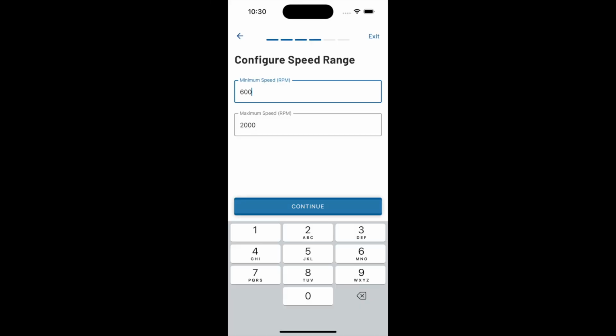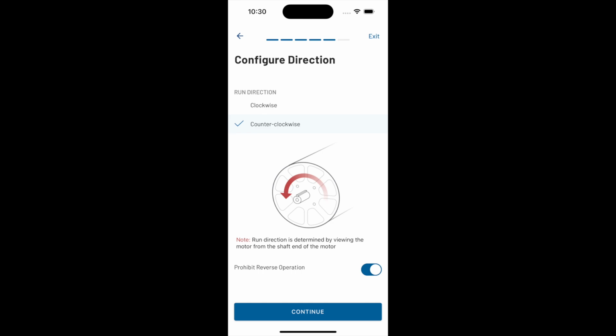Next, you will configure the min and max speed. Find the max speed on the old motor nameplate and enter this value into the app. Next, you will set motor run direction. Make sure to set this value to the run direction of the old motor.